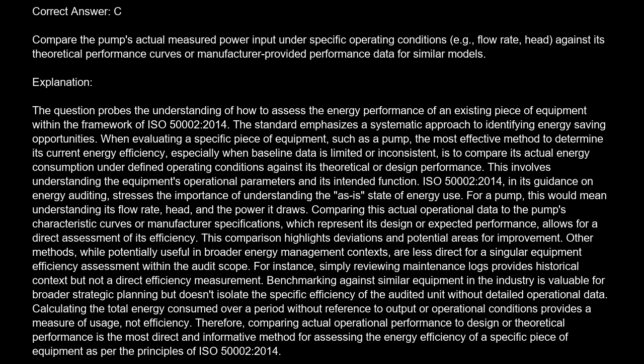Explanation: the question probes understanding of how to assess the energy performance of an existing piece of equipment within the framework of ISO 50002, 2014. The standard emphasizes a systematic approach to identifying energy-saving opportunities. When evaluating a specific piece of equipment, such as a pump, the most effective method to determine its current energy efficiency, especially when baseline data is limited or inconsistent, is to compare its actual energy consumption under defined operating conditions against its theoretical or design performance. This involves understanding the equipment's operational parameters and its intended function.